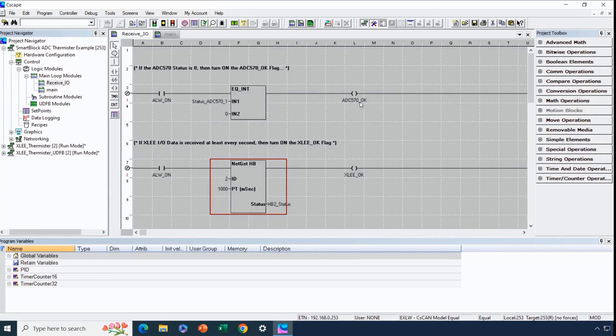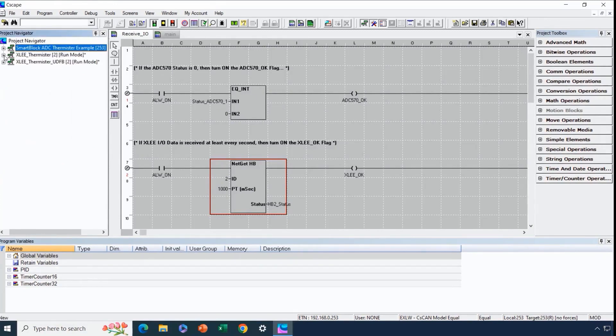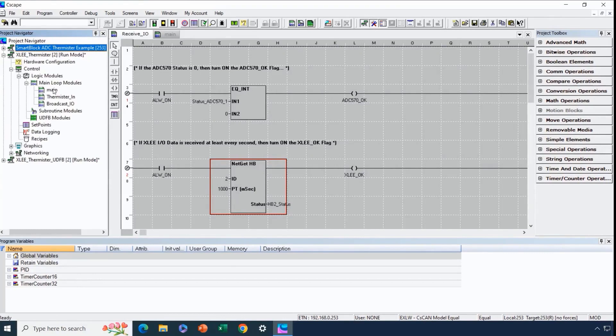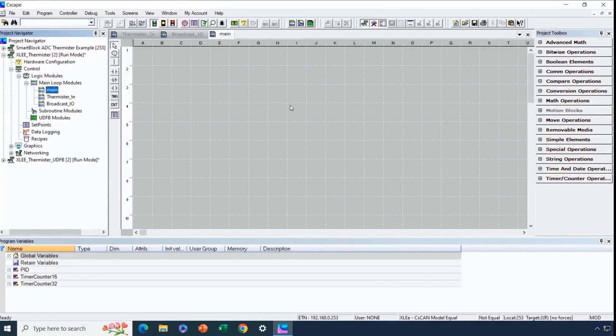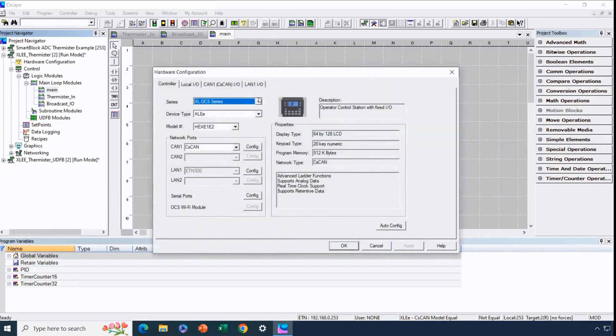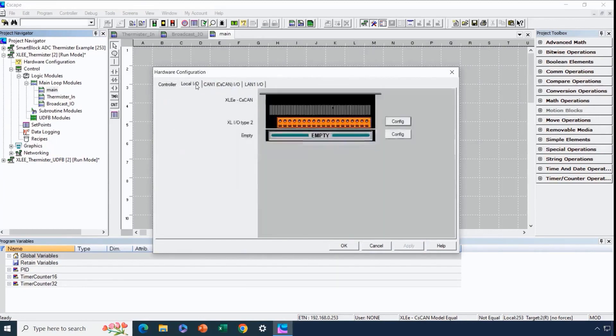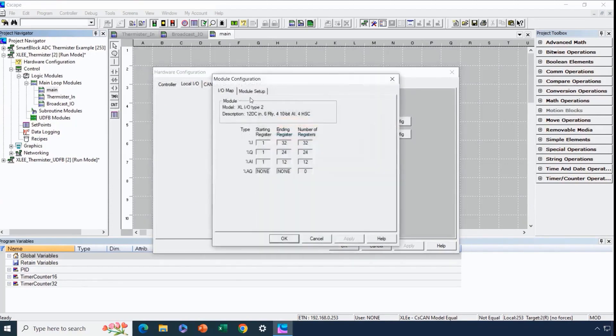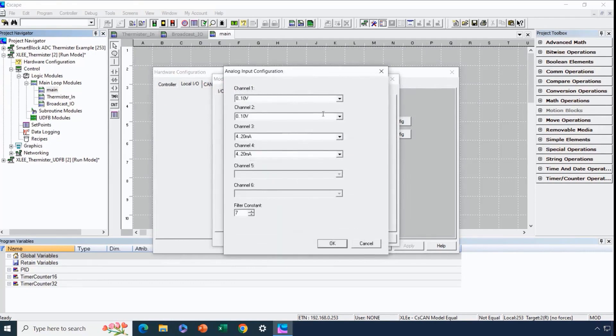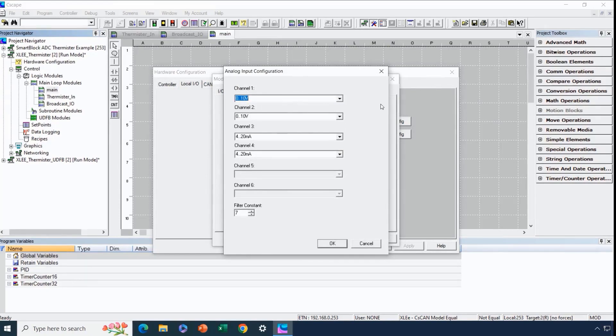There's a bit more involved in the XL series thermistor option, so we'll look at that now. We'll start in the main loop and go back into hardware configuration. This time we'll look at the XLE, then local I/O since this is a built-in I/O option. We select config, then module setup, and go to analog in. In the XL series configuration, there won't be thermistor as an option, as thermistor support was added after the fact as a special order. When using a thermistor with the special order XL series option, you need to select voltage as your input range for any channel supporting thermistor.